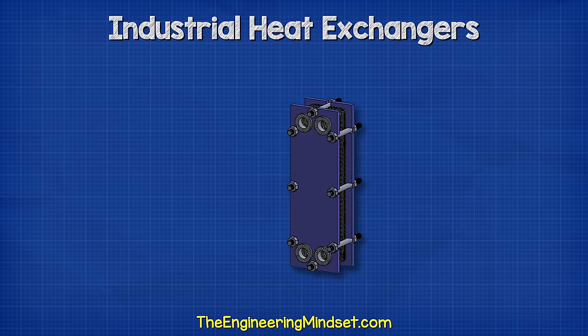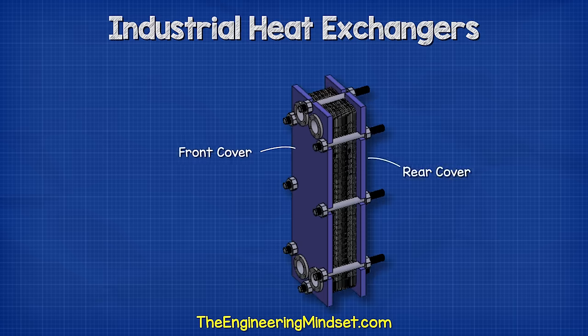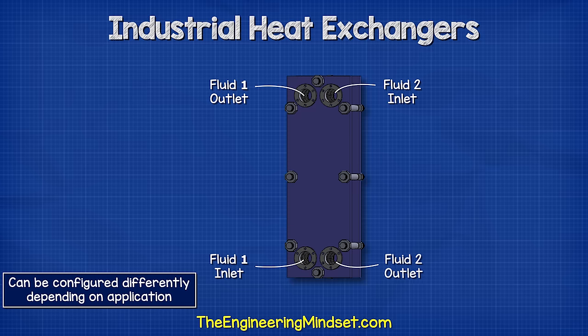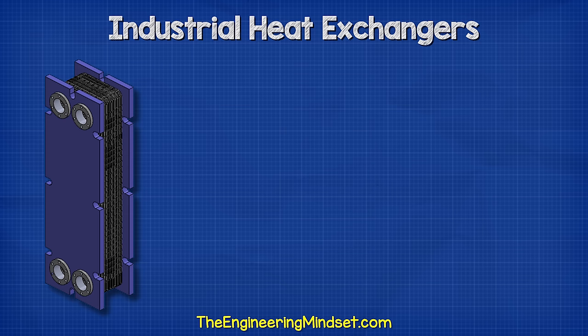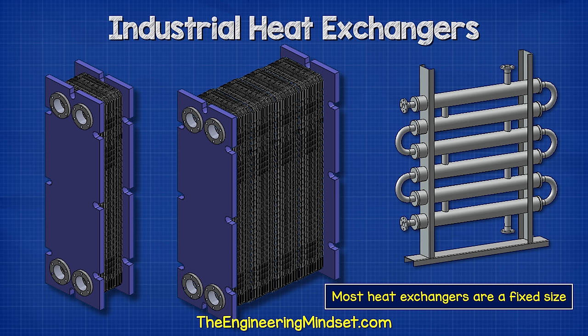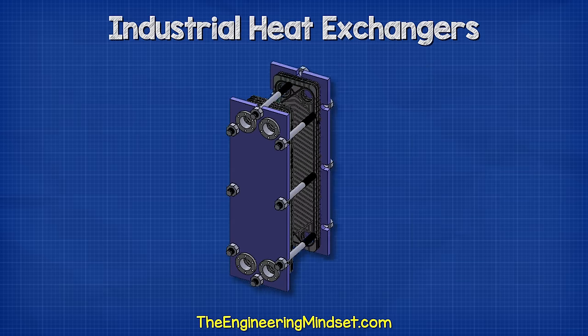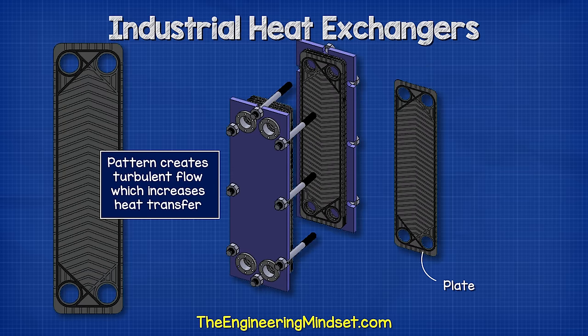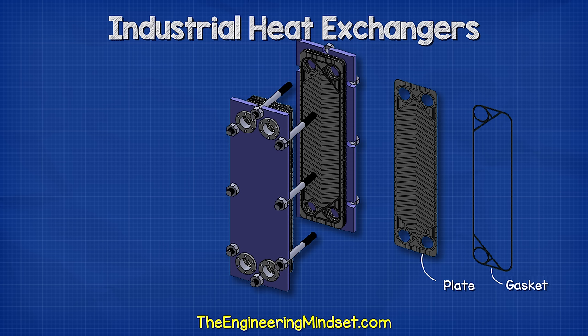Industrial plate heat exchangers look something like this. They consist of a thick metal cover on the front and rear of the unit, typically made from mild steel, with two inlets and two outlets, normally flange connections. In most designs, all four ports are located on the front plate, which allows the heat exchanger to be easily extended or reduced to accommodate future changes in operation — most heat exchangers do not have this ability. Between the end covers we find a number of plates, which are thin sheets of metal with a pattern stamped into them. These patterns help direct the fluids and create very turbulent flow, which increases heat transfer. Between each plate is a seal known as a gasket, typically made from rubber.